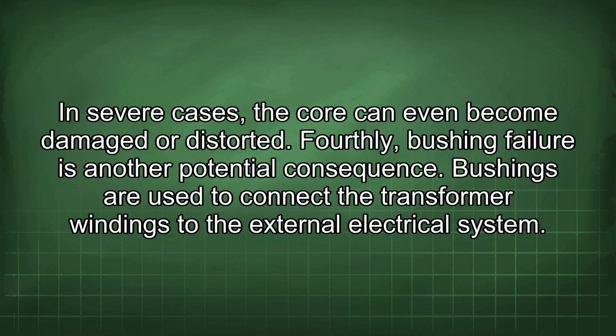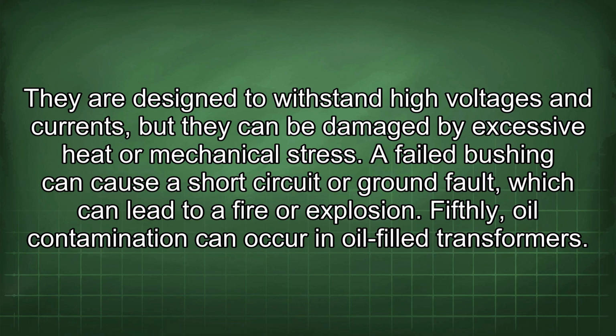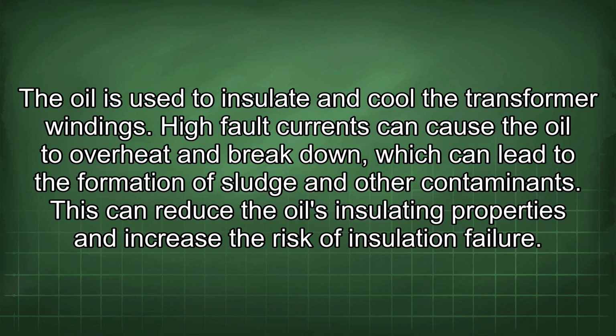Fourthly, bushing failure is another potential consequence. Bushings are used to connect the transformer windings to the external electrical system. They are designed to withstand high voltages and currents, but they can be damaged by excessive heat or mechanical stress. A failed bushing can cause a short circuit or ground fault, which can lead to a fire or explosion. Fifthly, oil contamination can occur in oil-filled transformers. The oil is used to insulate and cool the transformer windings. High fault currents can cause the oil to overheat and break down, which can lead to the formation of sludge and other contaminants. This can reduce the oil's insulating properties and increase the risk of insulation failure.